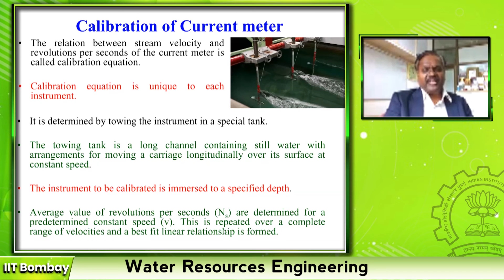I think this is the explanation for this. The towing tank is a long channel containing still water with arrangements for moving a carriage longitudinally over its surface. They are all controlled by computers so that you measure all the parameters. The instrument to be calibrated is immersed at a specified depth. The average value of revolutions per second is determined for a predetermined constant speed v. This is repeated over a complete range of velocities and the best fit linear relationship is formed, and that equation is nothing but the calibration of the current meter.